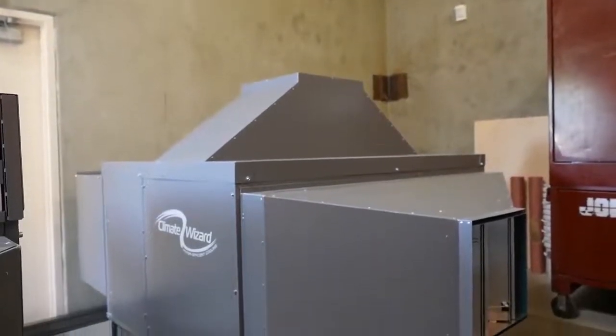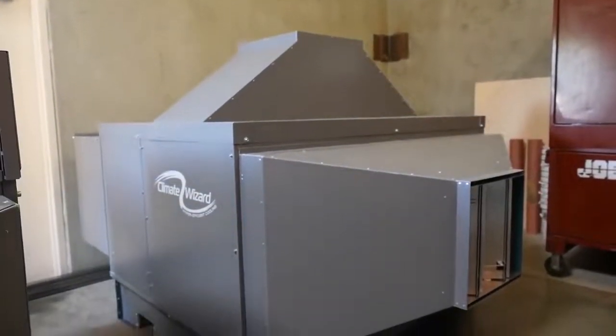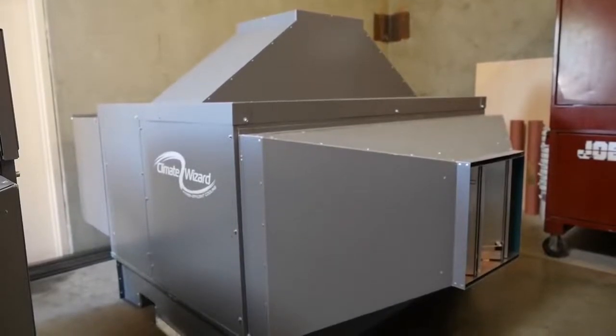We built our own model, got the ambient up to 130 degrees. We're still supplying supply temperature in the range of 55 degrees. This is using refrigerant R718, which is water. So their cost of ownership and cost of operation is so simple that the overall effect is the payback is so short in period of time that there's really no resistance to the purchase.